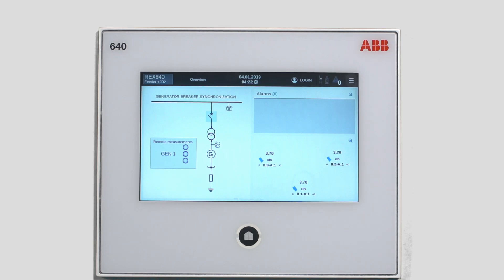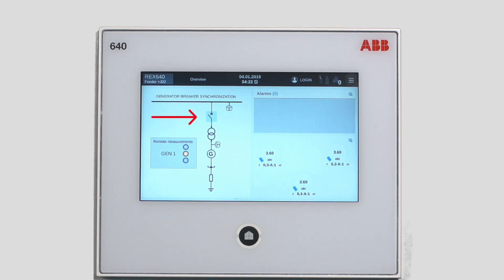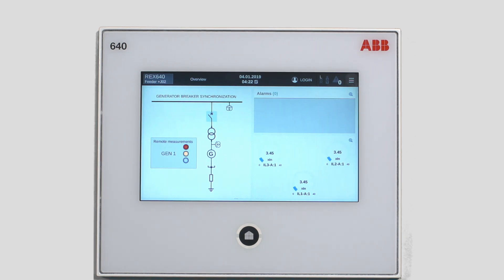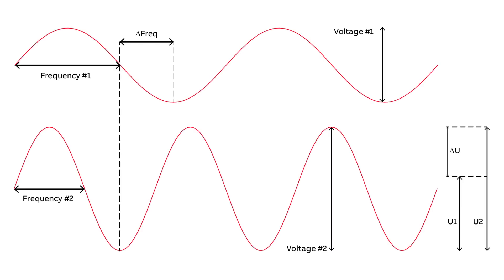The controllable primary objects, here a generator block transformer, are indicated by a grey background square in the single line diagram. Since there is a generator in question, you cannot just close the breaker. Voltage, frequency and phase angle across the breaker need to be matched before closing it.